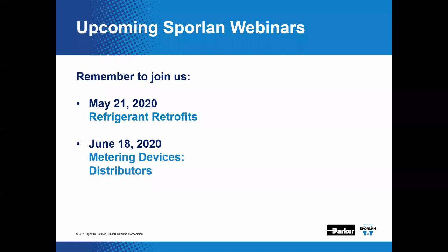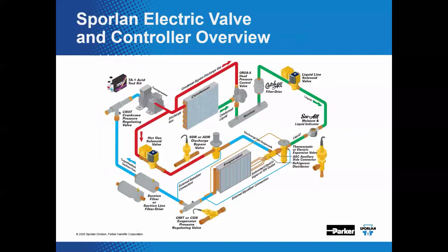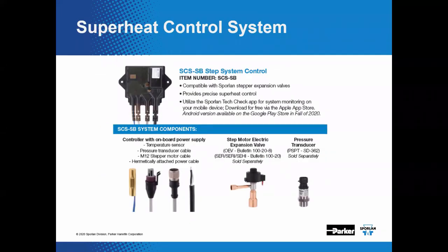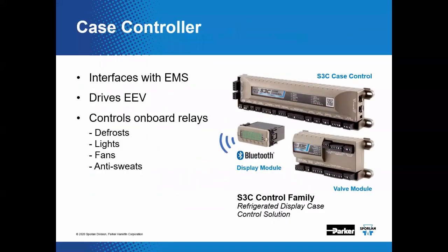Exactly. Do you have any other questions there, Glenn, that we ought to address while we got a little time? Here's one. Can the valve modulate on temperature while maintaining a minimum superheat? Now, what you're actually saying is, can the valve modulate the case temperature, is what it sounds like, while maintaining superheat? And the fact of the matter is no. This is a superheat controlling valve. That is all the valve is meant to do. To maintain temperature in the case, you have other controls inside the system, such as an evaporator pressure regulator or other things. The electric expansion valve is meant to control superheat and superheat only.